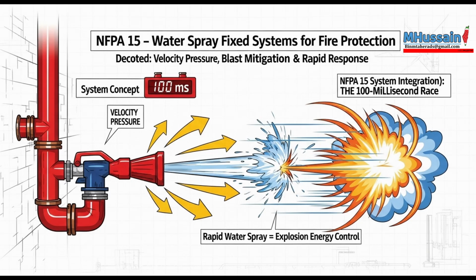So UHS is about stopping that fire front before it transitions into a full blast or detonation, or while it's still growing in an open area. Exactly that. Intervening incredibly early, according to 12.1.3. And the performance metric here is just astounding. Response time from detection to water actually flowing at the nozzle must be less than or equal to 100 milliseconds. That's 12.2.2. 100 milliseconds. Faster than you can blink. The system has to go from quiescent to fully discharging in literally a tenth of a second.